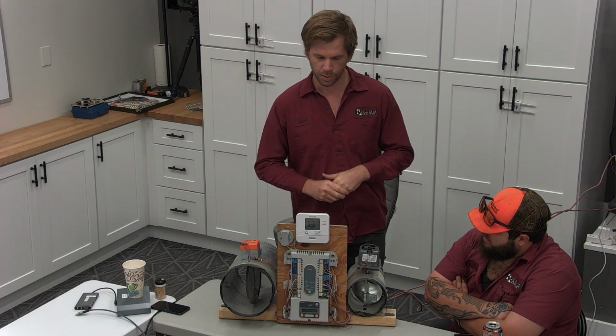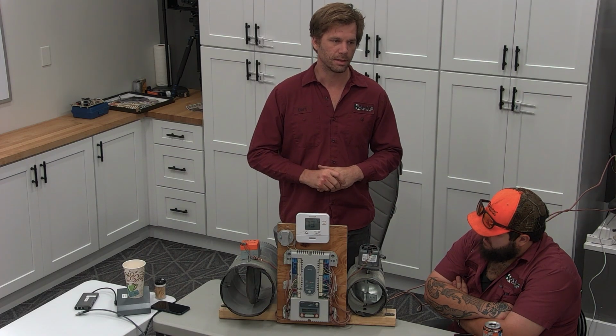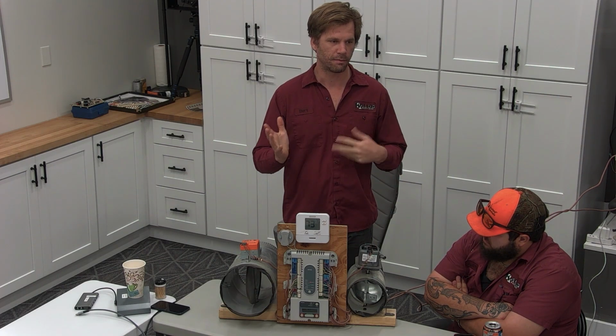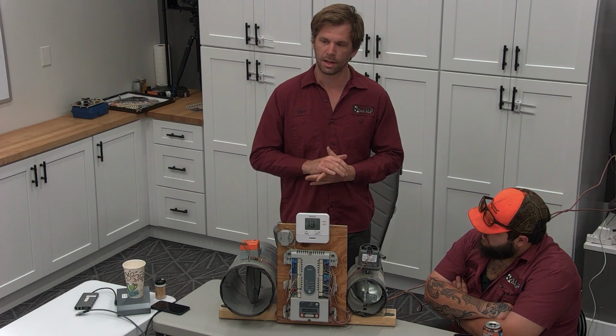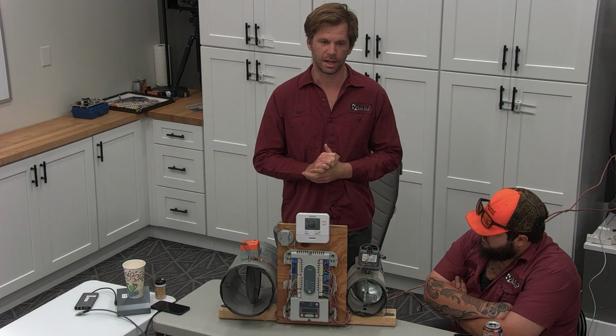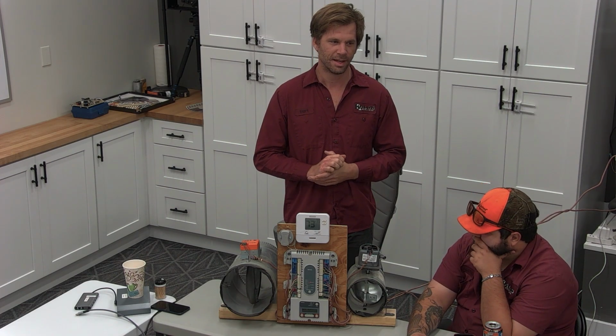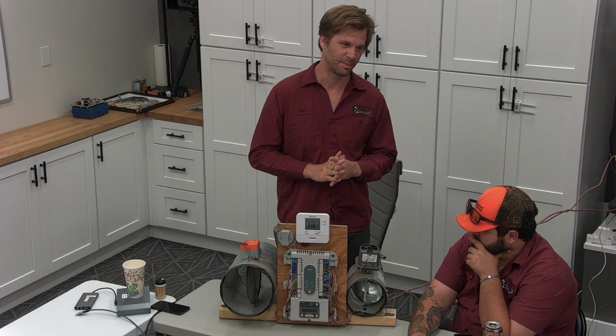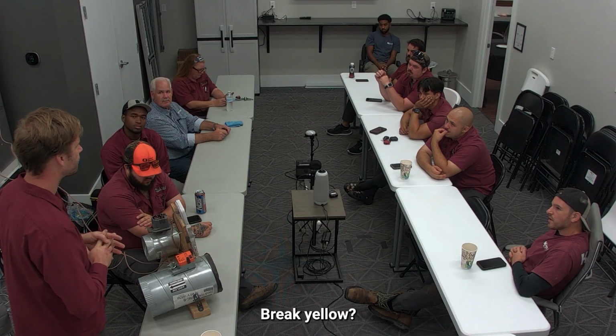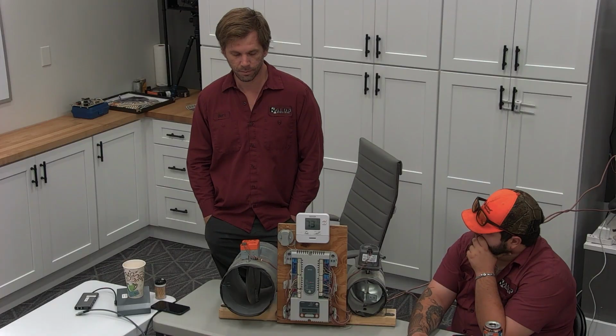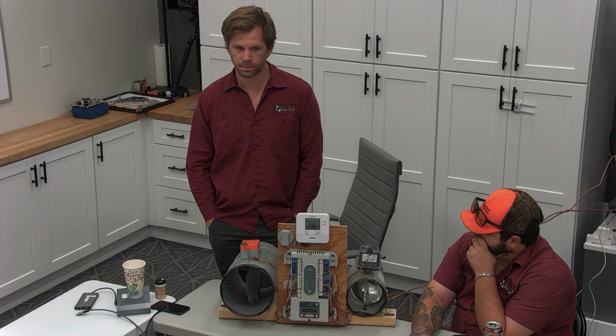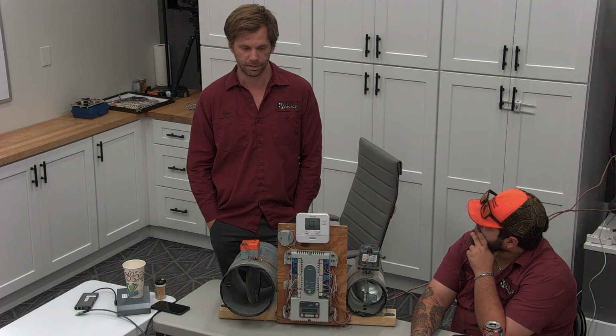So you could put the freestat as a float switch to kill main power, but then you constantly have things coming off and resetting. You don't want to do that anywhere in the vacation area where they might have alarm thermostats that reset to heat pumps or to a non-heat pump system every time it kills power. Break yellow? No, you could, but I also don't like that. I don't like a compressor coming on and off. You could break red on a damper system, that would be fine. But my favorite way is just to tie it in where the DAT sensor is. Or I'm sorry, don't ever tie it in where the DAT sensor is.